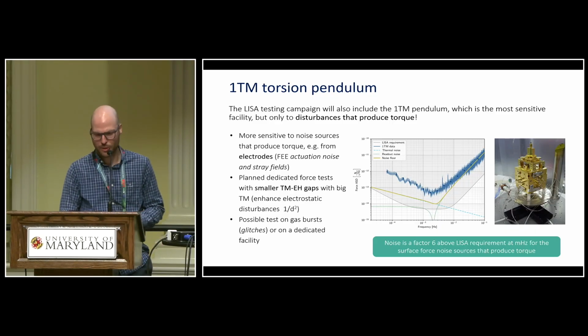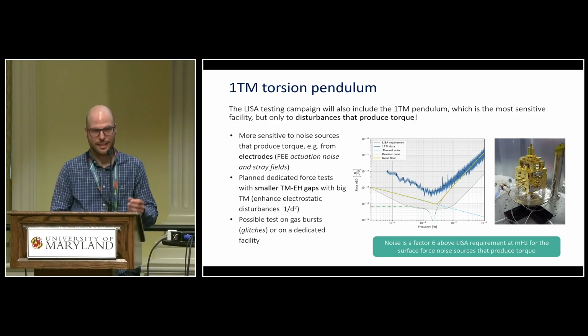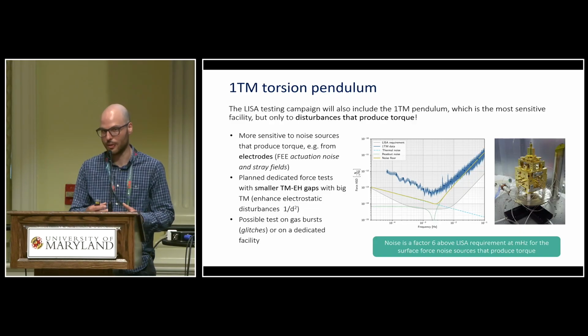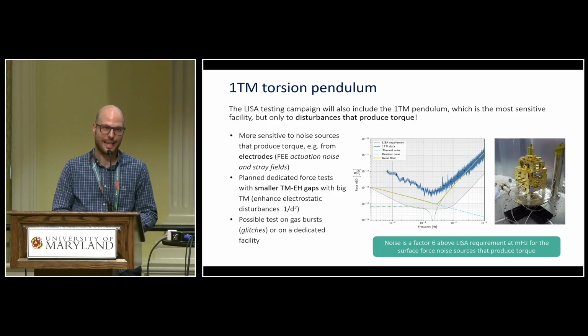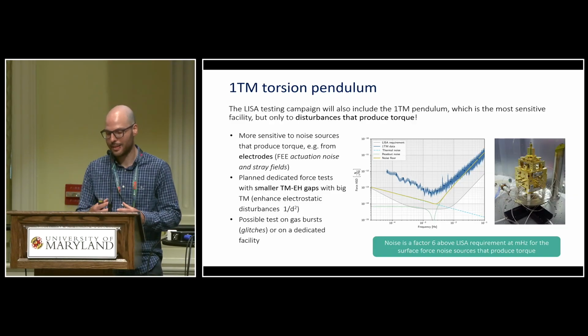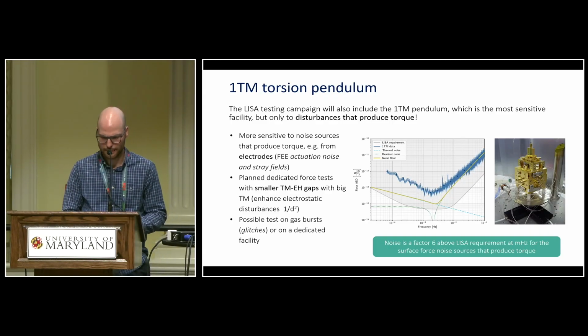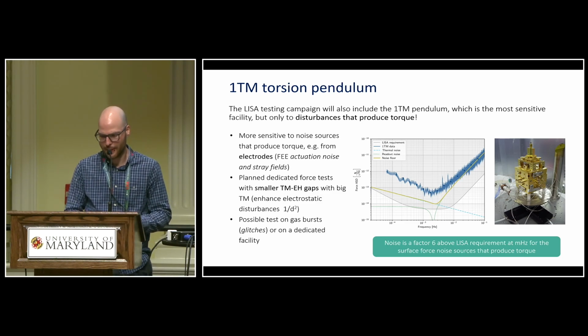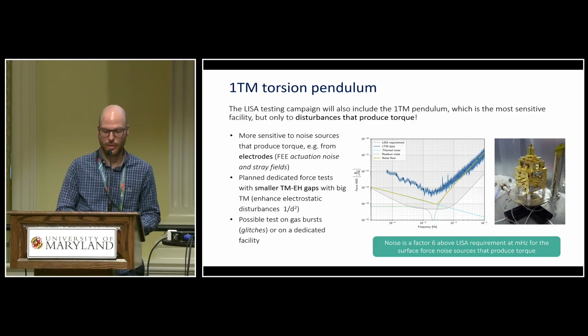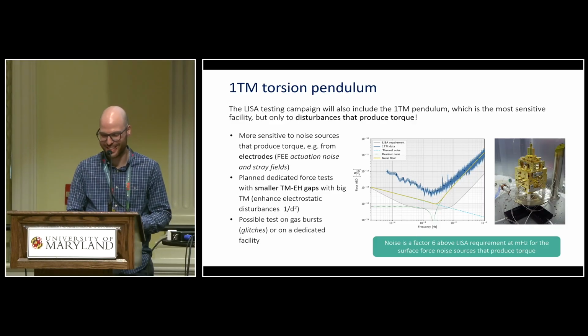The single test mass torsion pendulum is very, very sensitive, but as I mentioned before, sensitive to effects that produce a torque. This makes it ideal for measuring, for example, disturbances coming from the electrodes and from the front-end electronics. We are also planning to improve its sensitivity to this effect by reducing the test mass to electrode housing gaps by mounting a bigger test mass. We are also envisioning using it for dedicated tests on gas bursts, more commonly known as glitches, that were observed in LISA Pathfinder.